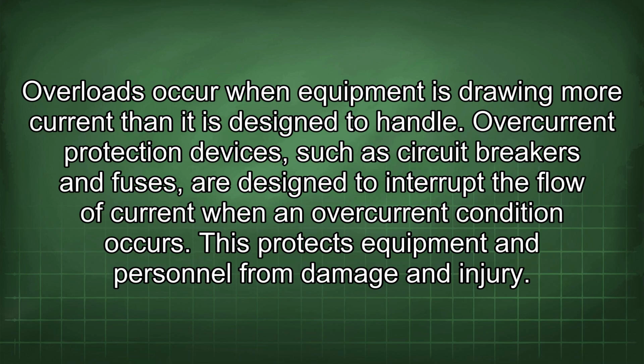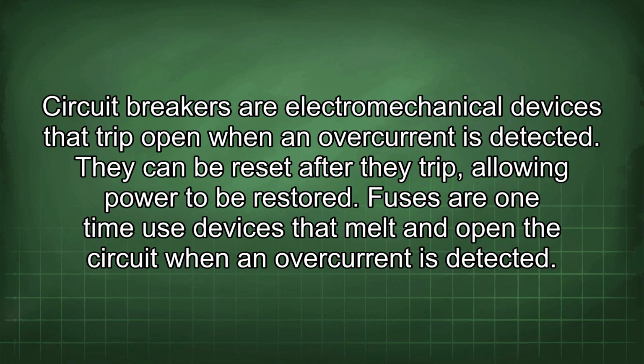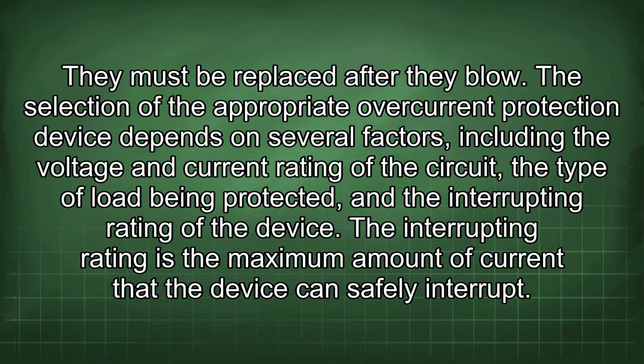Overcurrent protection devices, such as circuit breakers and fuses, are designed to interrupt the flow of current when an overcurrent condition occurs. This protects equipment and personnel from damage and injury. Circuit breakers are electromechanical devices that trip open when an overcurrent is detected. They can be reset after they trip, allowing power to be restored. Fuses are one-time use devices that melt and open the circuit when an overcurrent is detected. They must be replaced after they blow.